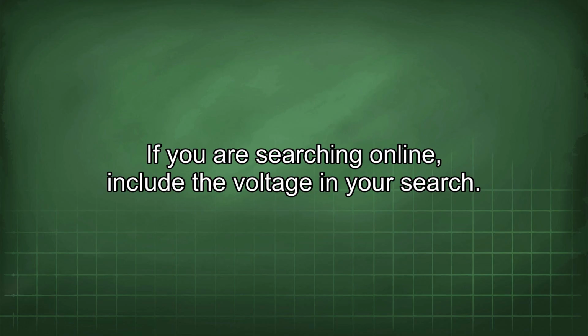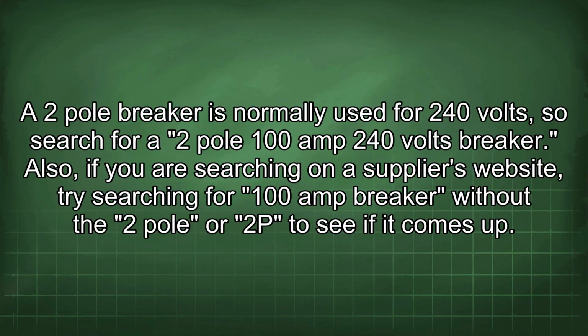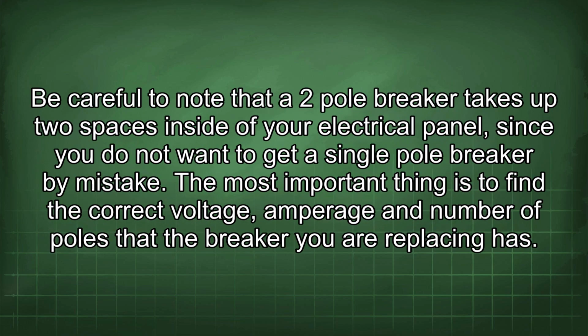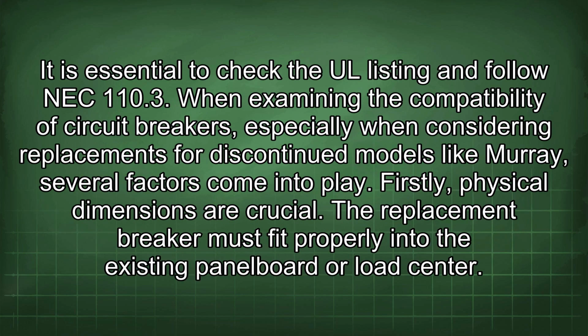If you are searching online, include the voltage in your search. A 2-pole breaker is normally used for 240 volts, so search for a 2-pole 100 amp 240 volts breaker. Also, if you are searching on a supplier's website, try searching for 100 amp breaker without the 2-pole or 2P to see if it comes up. Be careful to note that a 2-pole breaker takes up 2 spaces inside of your electrical panel, since you do not want to get a single-pole breaker by mistake. The most important thing is to find the correct voltage, amperage, and number of poles that the breaker you are replacing has. It is essential to check the UL listing and follow NEC 110.3.